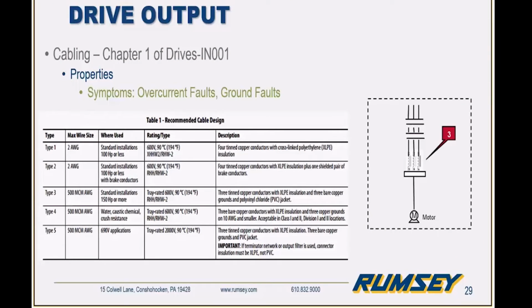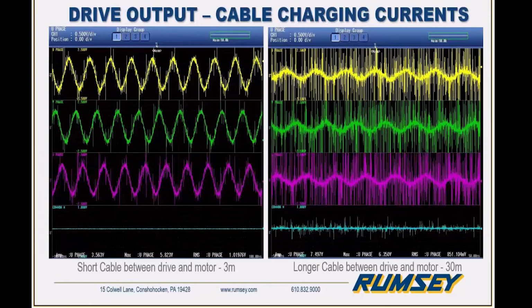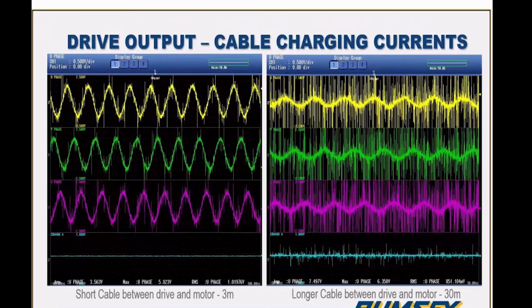Moving on to cable charging currents. Most times we see smaller drives that are most susceptible to the cable charging currents, typically 2 horsepower and under. On the left-hand side here, we see a relatively short lead length of 3 meters between the drive and the motor, and we can see the output waveform. On the right-hand side, the motor lead length has increased to 30 meters, and we can see the resulting current output from that. Basically, in some cases, especially when we have smaller drives, the cable charging currents can be greater than the current rating of the drive, and we can experience overcurrent faults on the drive.